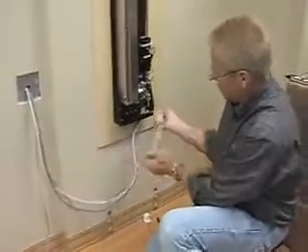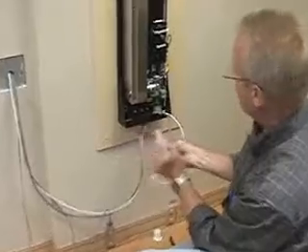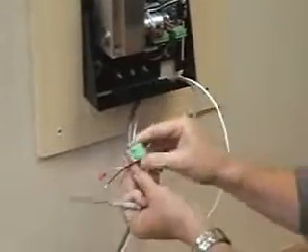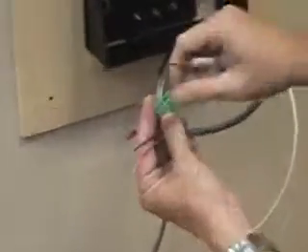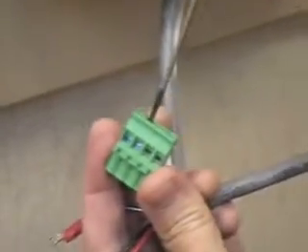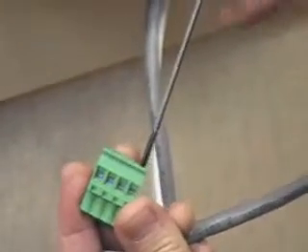Okay, now that we have these cables through, we're going to take this power cable and this connector. If you can see, there are screws on the top and openings in the side. The connector is big enough to take two power cables. Make sure these are twisted good.